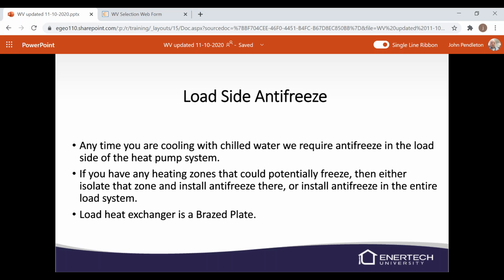So the heat exchangers are braze plates, and they do not handle freezing very well. You freeze it once, you might get lucky. You freeze it twice, you're probably going to be out of luck. They'll swell up and they'll break those plates. Then you got water in your refrigerant circuit, and it's a big nightmare. So make sure that we're installing antifreeze on the load and the source.